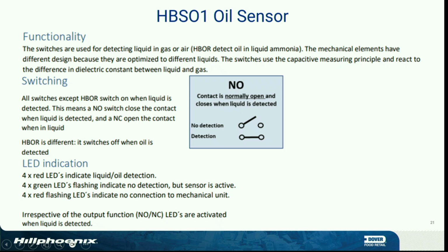It has 4 LEDs, which is basically just 4 LEDs around it. The red indicates liquid oil detection. LEDs flashing green means there's no detection, but the sensor is energized. And 4 red flashing LEDs indicate no connection to the mechanical unit. That's basically so you've lost connection between your sensor probe and the head element. All right? And when you get a new one, you can just change the head. There's no reason to change out the entire well.